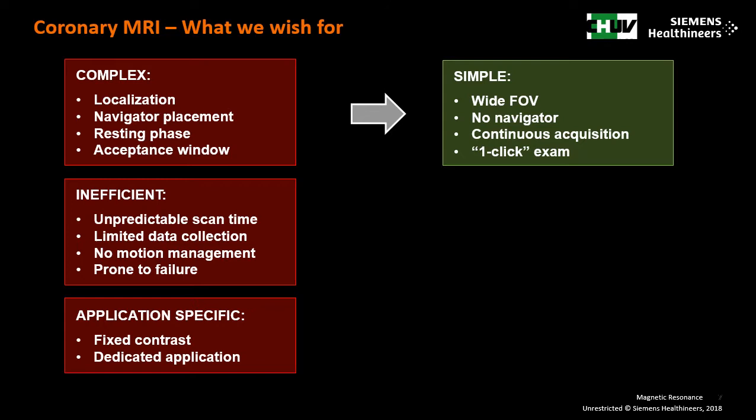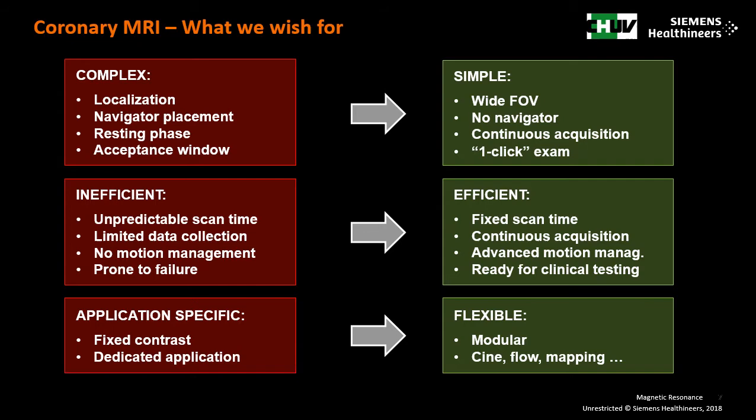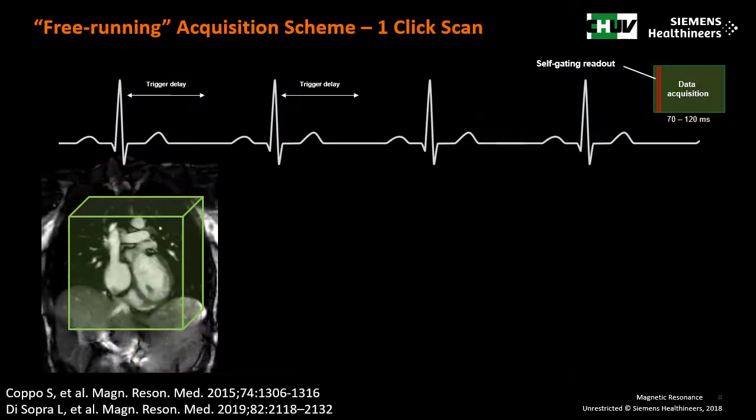This means a wide field of view that covers all the anatomy of the heart, no navigator placement, a one-click start, and a continuous acquisition. Secondly, the scan should become feasible in clinical routine, therefore we want a fixed scan time. This also means continuous acquisition and that we have to take care of motion management in an advanced manner in the reconstruction. Last but not least, we envision that the scan could be somewhat modular so that other information besides anatomy could be extracted, like cine, flow, and eventually mapping.